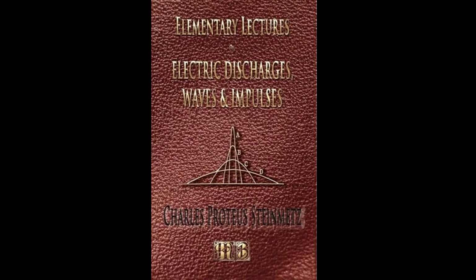become destructive, or may require serious consideration, as, for instance, is the case in governing high-head water powers. The column of water in the supply pipe represents a considerable amount of stored mechanical energy, when flowing at velocity, under load. If, then, full load is suddenly thrown off, it is not possible to suddenly stop the flow of water, since a rapid stopping would lead to a pressure transient of destructive value, that is, burst the pipe. Hence the use of surge tanks, relief valves, or deflecting nozzle governors.